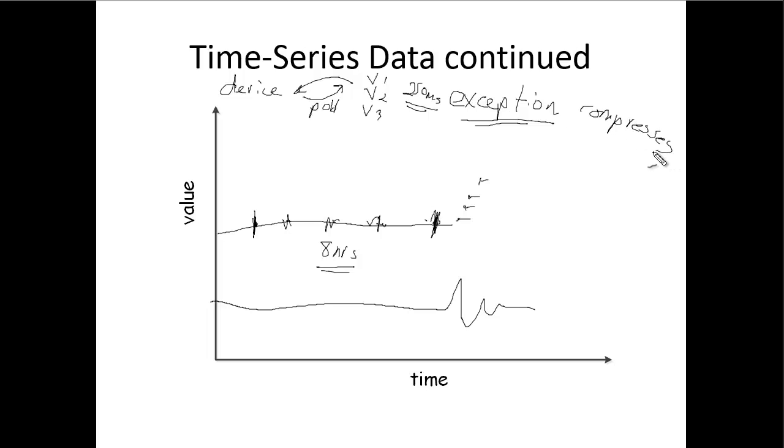And so now if I go and I look at what's in my database, I'll have a reading here, I'll have a reading here, and I'll have a bunch of readings in here. But I've kind of optimized it because I didn't take a bunch of readings in here. So I'm going to store less data. Okay, so my storage space is going to be less. And my speed of retrieval is going to be better because I'll read a thing here, and I'm going to read a thing here, and then I'm going to read a bunch here. But I'm optimizing both of those. Okay, so that's kind of a neat thing. So that's exception-based reporting. Now I can actually get a little more sophisticated than that. So we're going to talk about that in the next step.